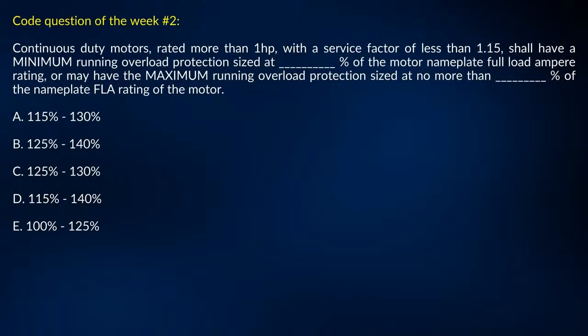Oh, you got a code question of the week. Cool. Yeah. So continuous duty motors rated more than 1 horsepower with service factor less than 1.15 shall have a minimum running overload protection sized at blank % of the motor nameplate full load ampere rating, or may have a maximum running overload protection sized at no more than blank % of the nameplate full load rating of the motor.